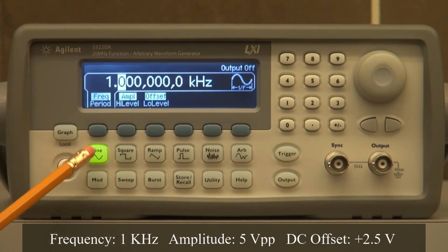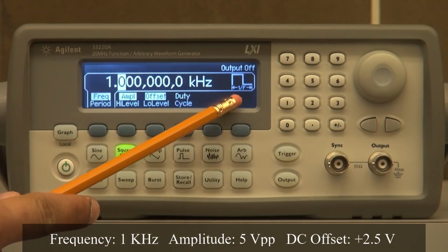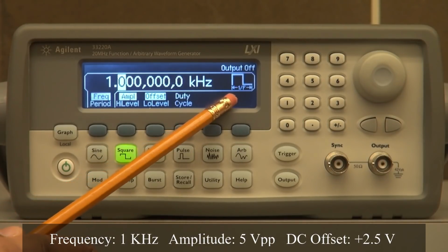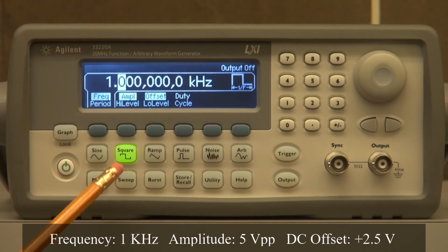Note that they all have markings on the button identifying their shape, and were you to press another button, it lights up and the graphic on the LCD screen changes to represent the shape of the function you have selected. Let's press the sine button. After this, we can use the keypad, knob, or context-dependent soft keys to edit the parameters of the sine wave. First, let's select the frequency of our desired output waveform.